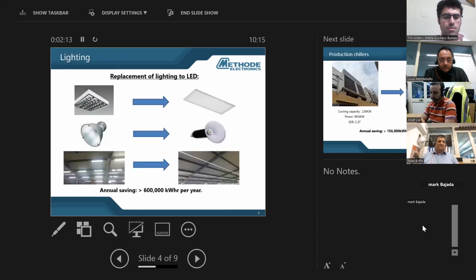Starting from lighting, during the last 10 years, we have replaced all lighting, and we are now working all LED lighting. Basically, the fluorescent tubes were replaced by LED panels. The metal halides have been replaced by LED high bays. We calculate that we have made more than 600,000 kilowatt-hour savings per year. Basically, during the replacement, we calculate that there is roughly around 50% saving, especially when replacing metal halide with LED high bays.